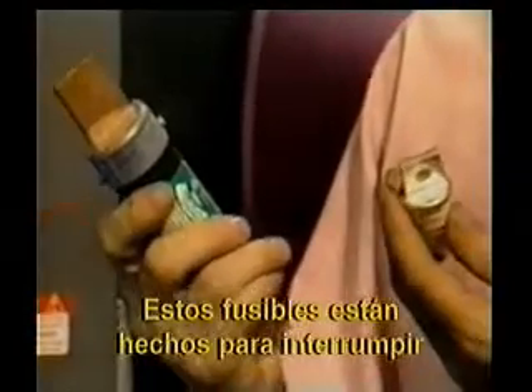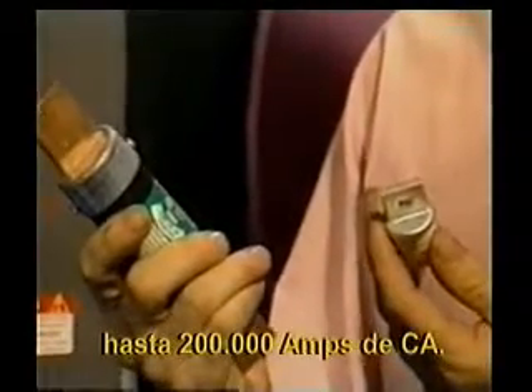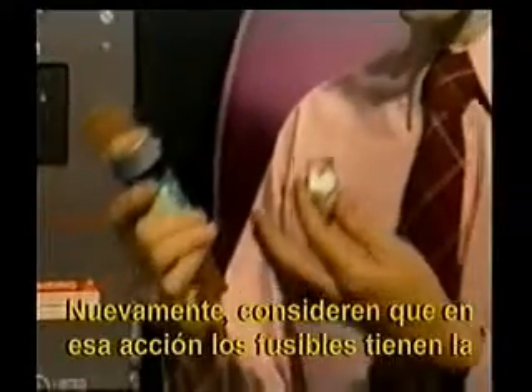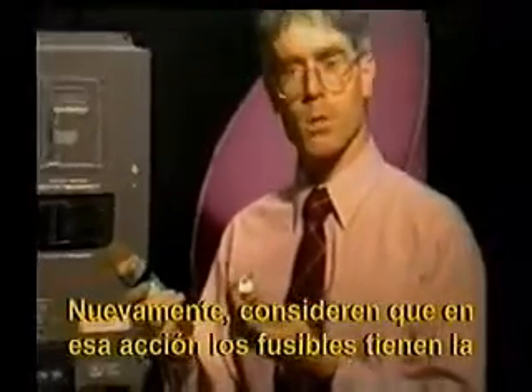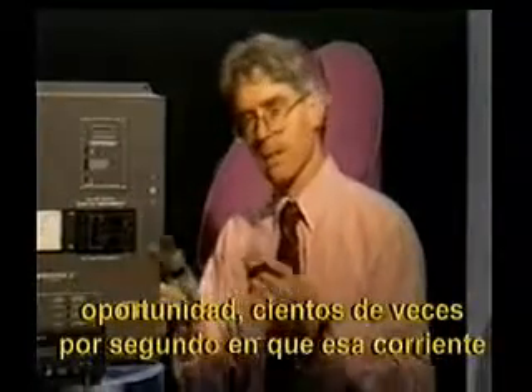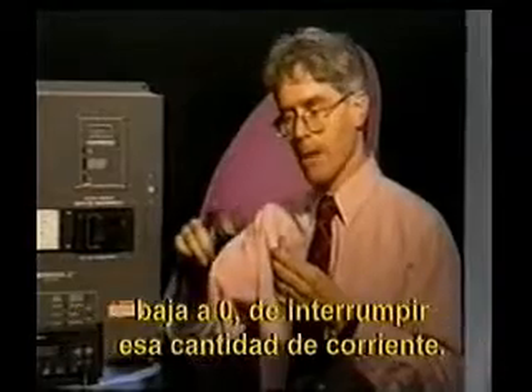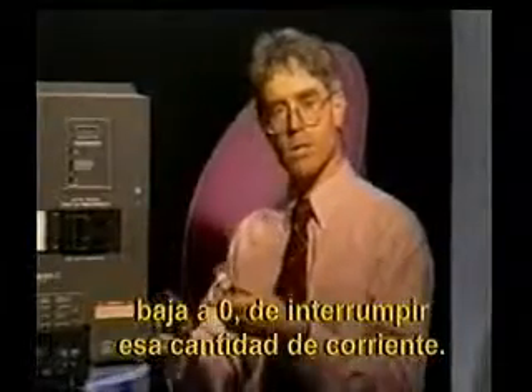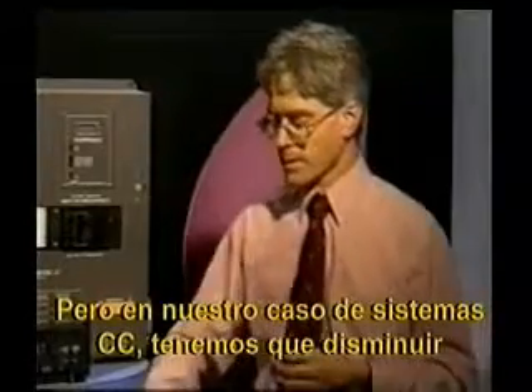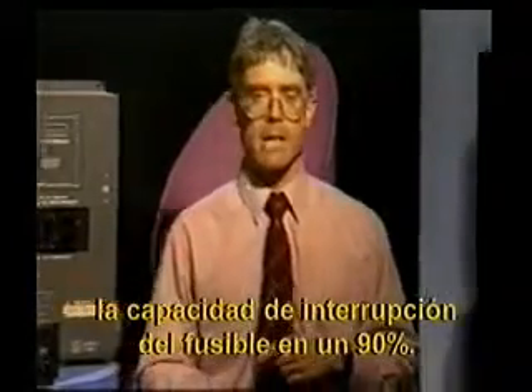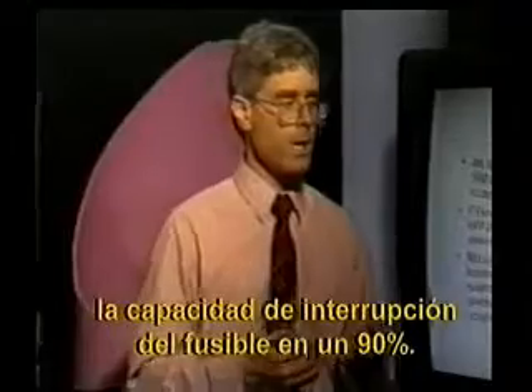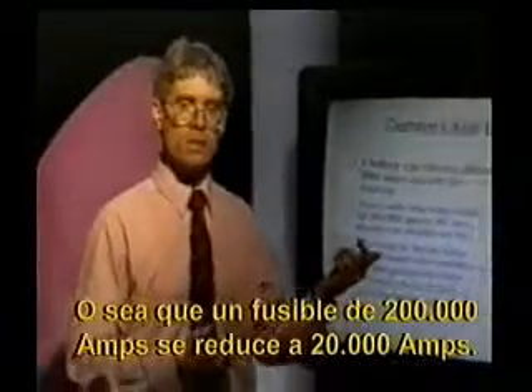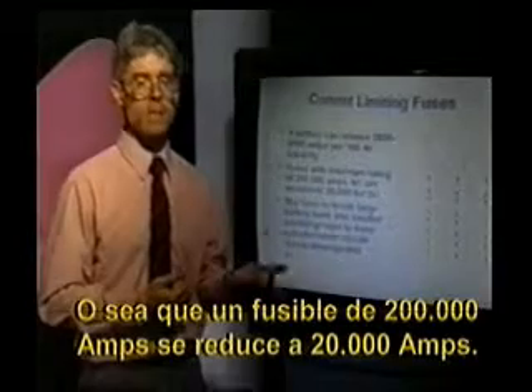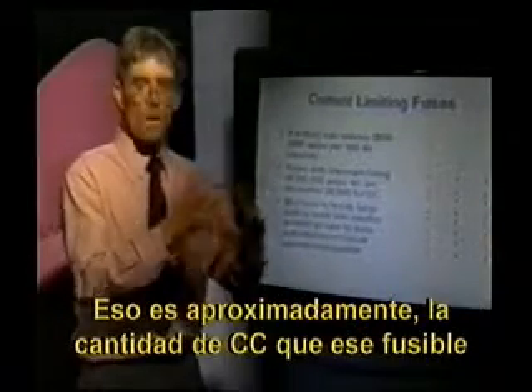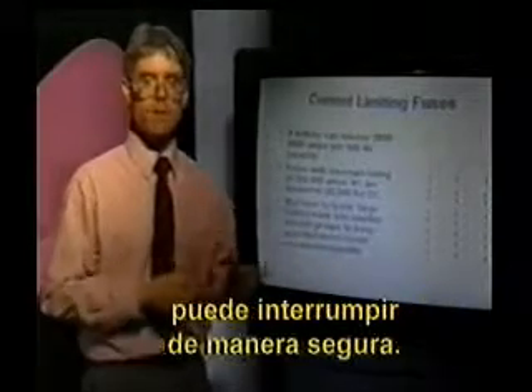These fuses are designed to break 200,000 amps of AC current. They can, in other words, they're designed to be able to break up to that much current, AC. Again, consider the fact that when they do that, they'll have an opportunity hundreds of times a second where that current goes to zero, so they can safely break that much current. But in our case of DC systems, we have to derate that current breaking capability, that interrupt rating of that fuse, by 90%. So a 200,000 amp fuse is derated to 20,000 amps. That's plus or minus roughly the amount of DC current that that fuse could safely break.